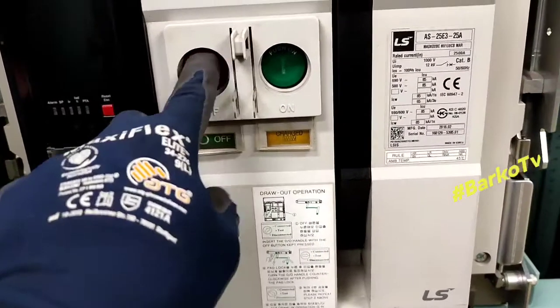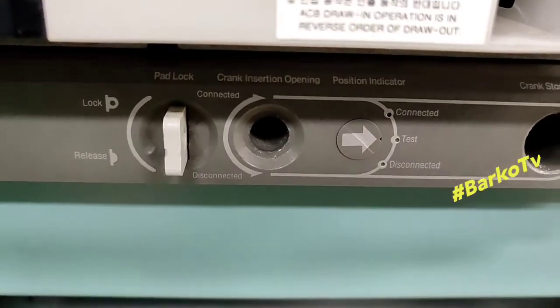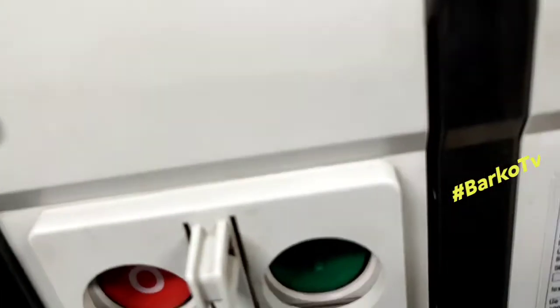The test position means the ACB is disconnected from your bus bar. Right now you can see the test position and the padlock is released. We will now go to full disconnection — disconnected means you can remove the ACB totally.